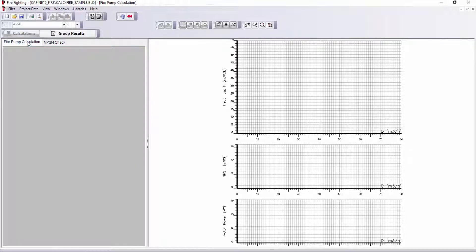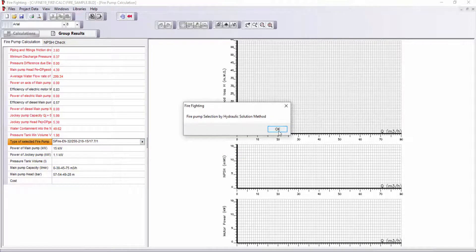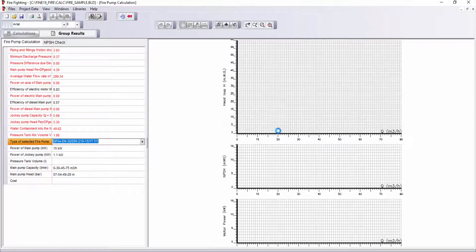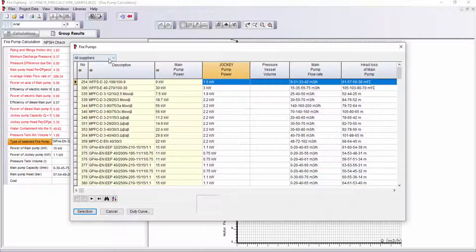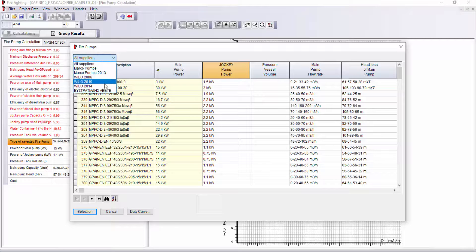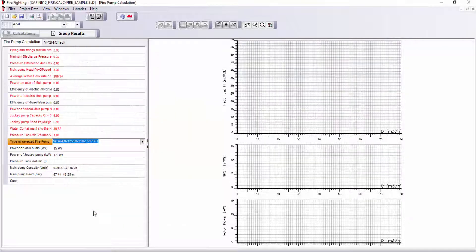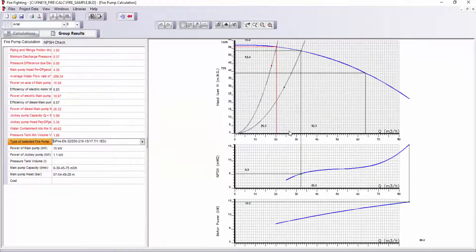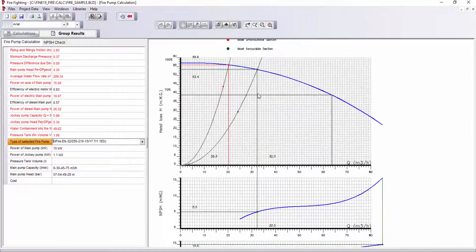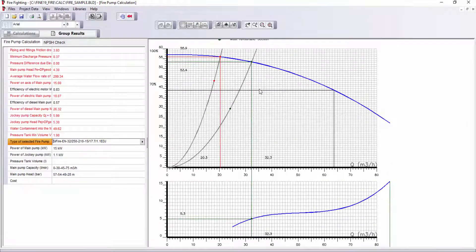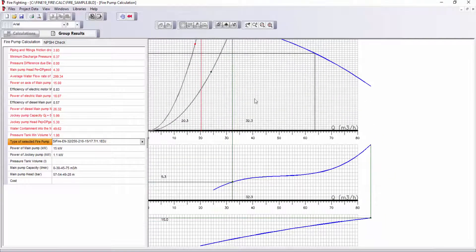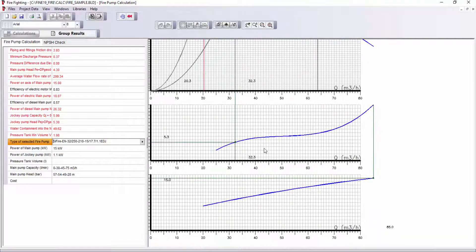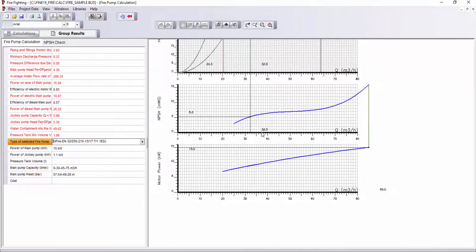Decide the appropriate type of fire pump from Type of Selected Pump. When you select the fire pump, you can see on the right side of the window the pump's curve. Check the NPSH in the next tab. By filling in the data that correspond to the project, you can see also the NPSH and motor curve under the pump curve.